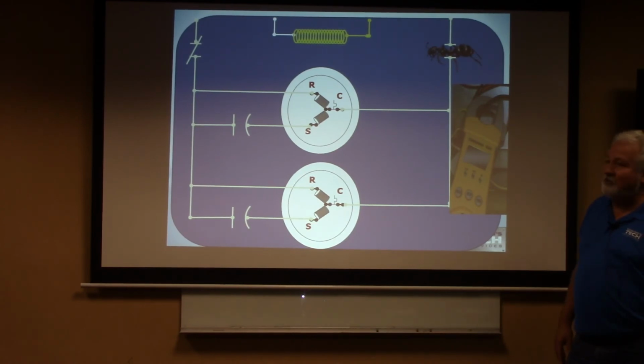All right, so we got that big old ant stuck in that contactor, and we're going to check here and here. What are we going to read? 240 volts, is that right? Sweet. How about here and here? 110 or 120. 110? 112? 114? Depends on where you're at.